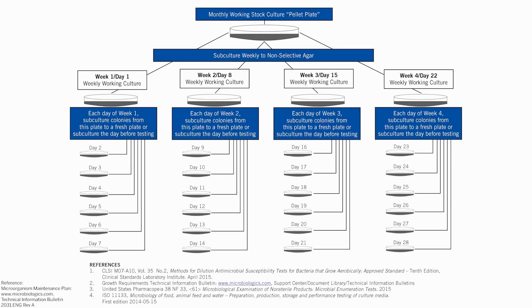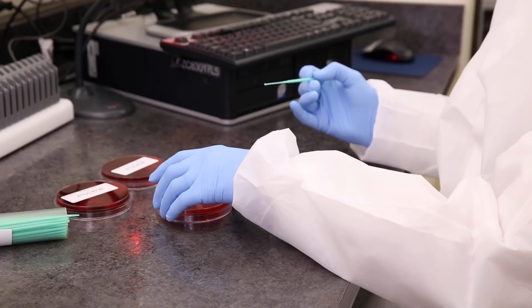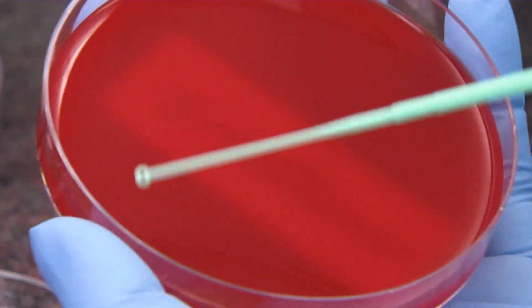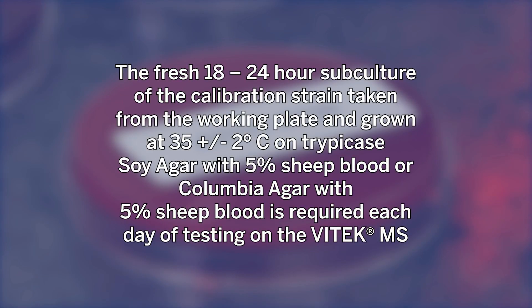After incubation, the stock plate is stored at 2 to 8 degrees Celsius and is used to subculture a weekly working culture plate on the same media — trypticase soy agar with 5% sheep blood or Columbia agar with 5% sheep blood. This working plate is incubated for 18 to 24 hours at 35 plus or minus 2 degrees Celsius. The working plate serves two purposes: it is used to make the calibrator spot on the first day post-incubation, and to subculture new calibrator plates for days 2 through 7. A fresh 18 to 24 hour subculture of the calibration strain is required each day of testing on the Vitek MS.